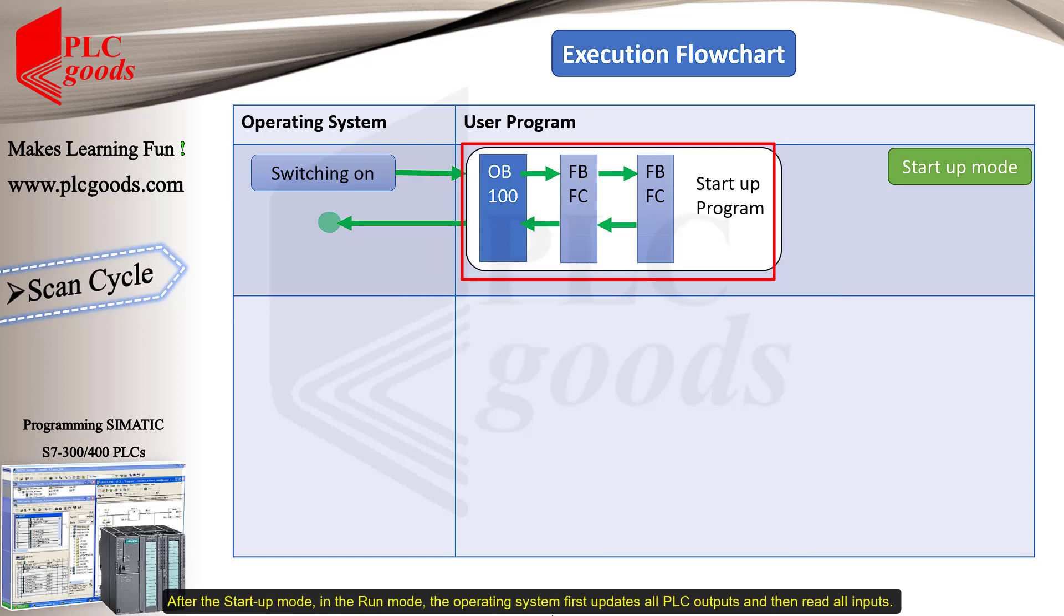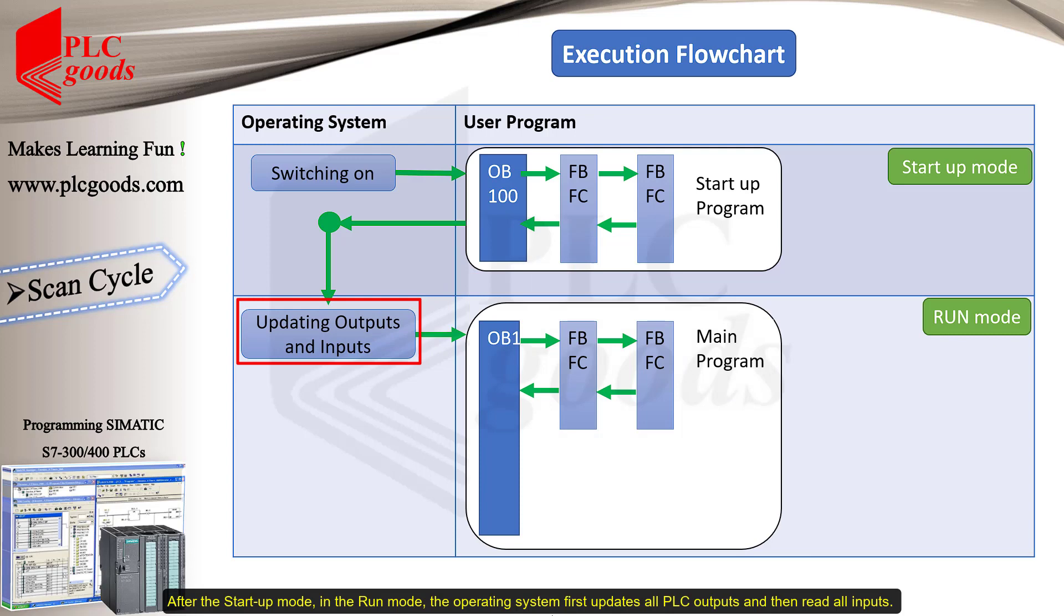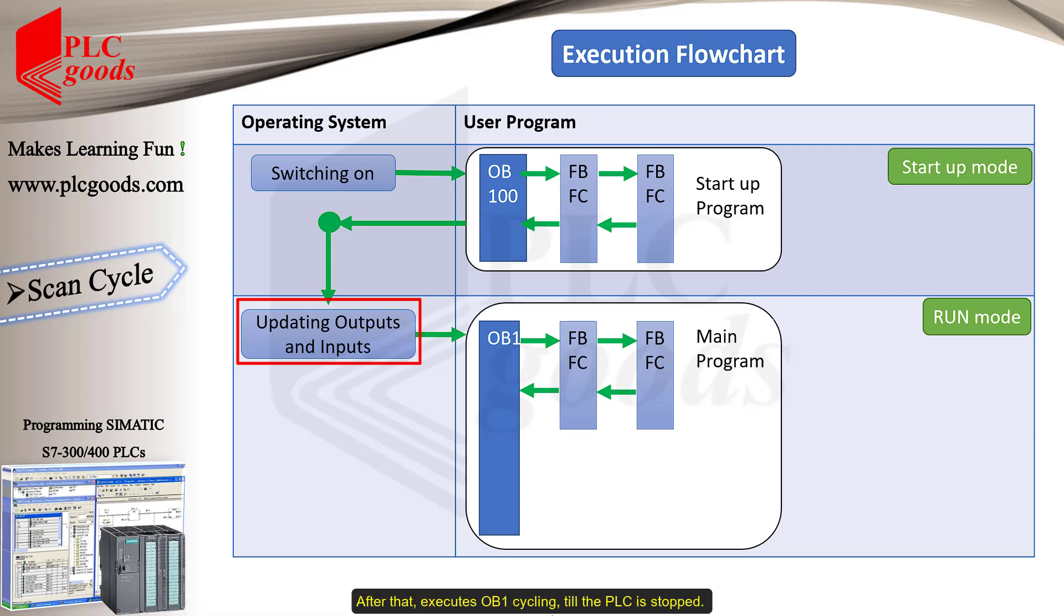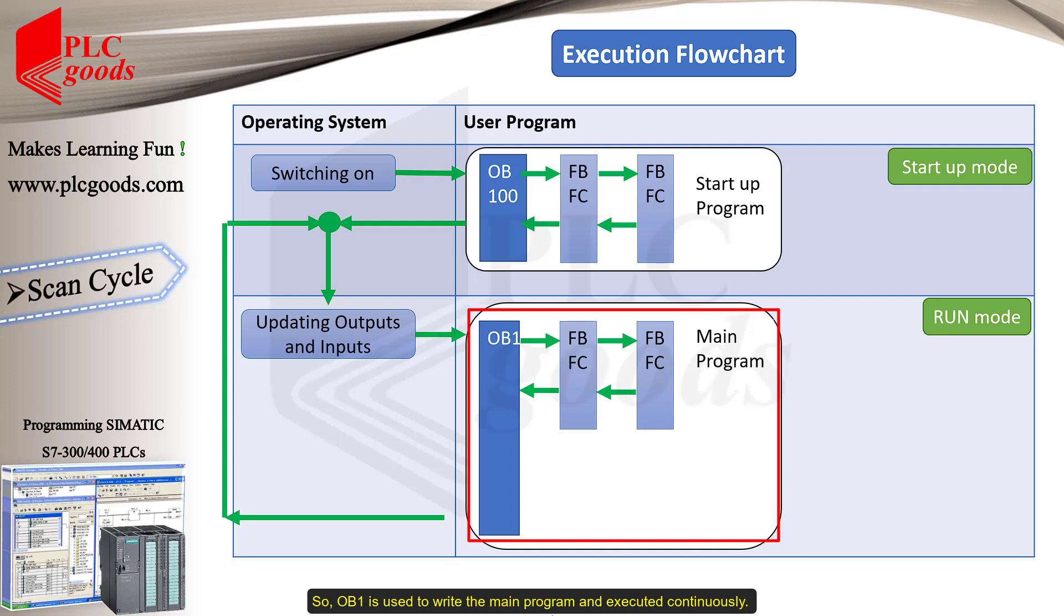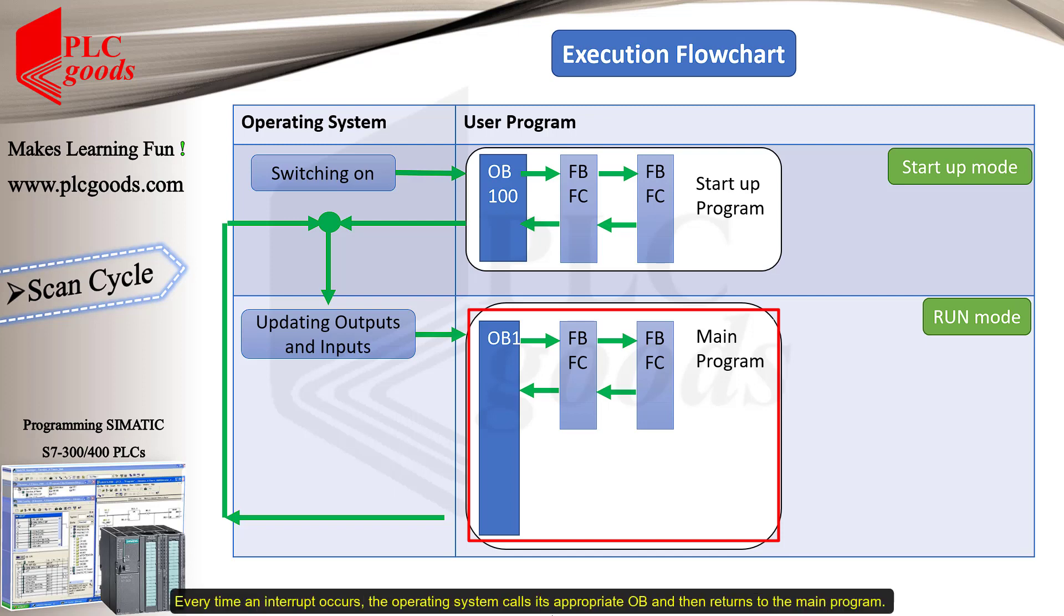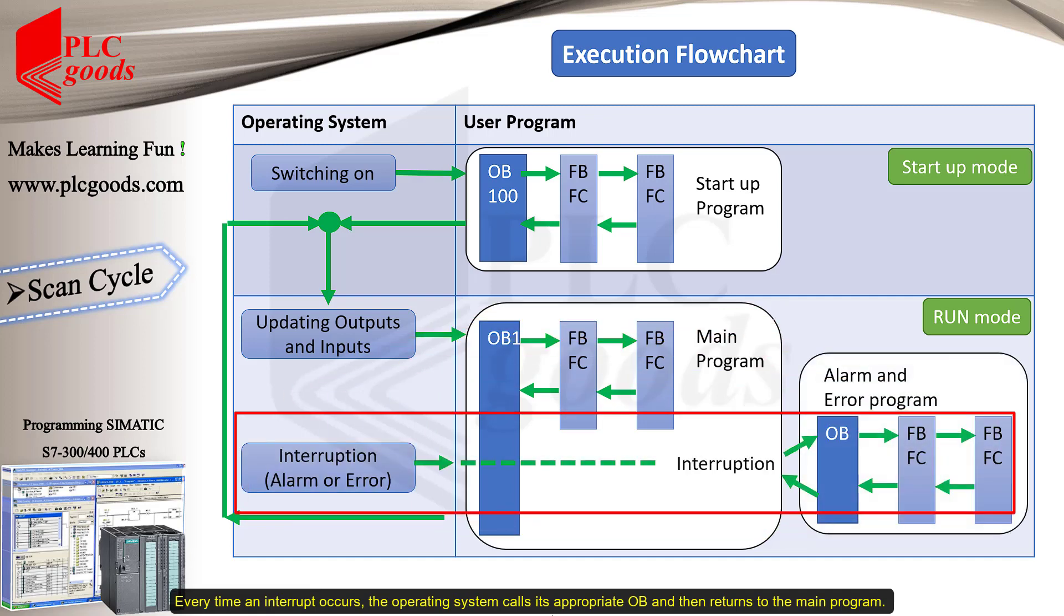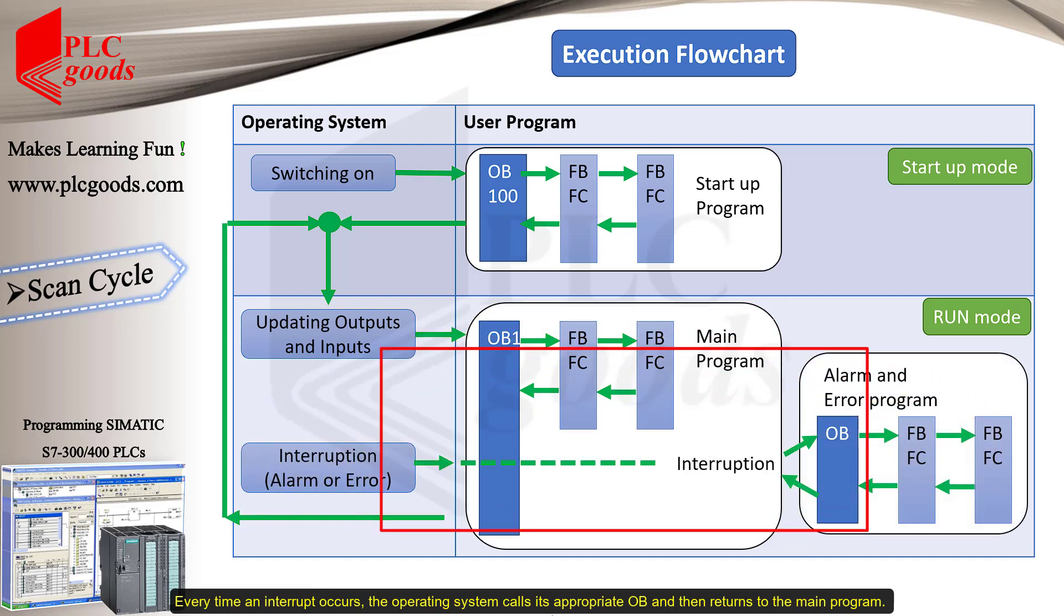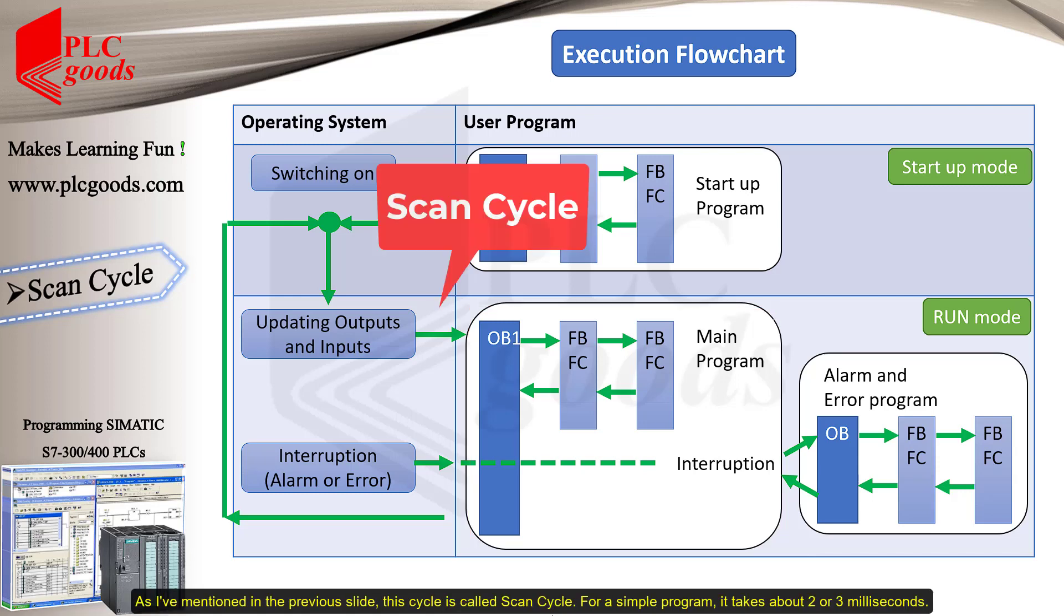After the startup mode, in the run mode, the operating system first updates all PLC outputs, and then reads all inputs. After that, it executes OB1 cycling till the PLC is stopped. So, OB1 is used to write the main program and executed continuously. Every time an interrupt occurs, the operating system calls its appropriate OB and then returns to the main program. As I mentioned in the previous slide, this cycle is called a scan cycle.